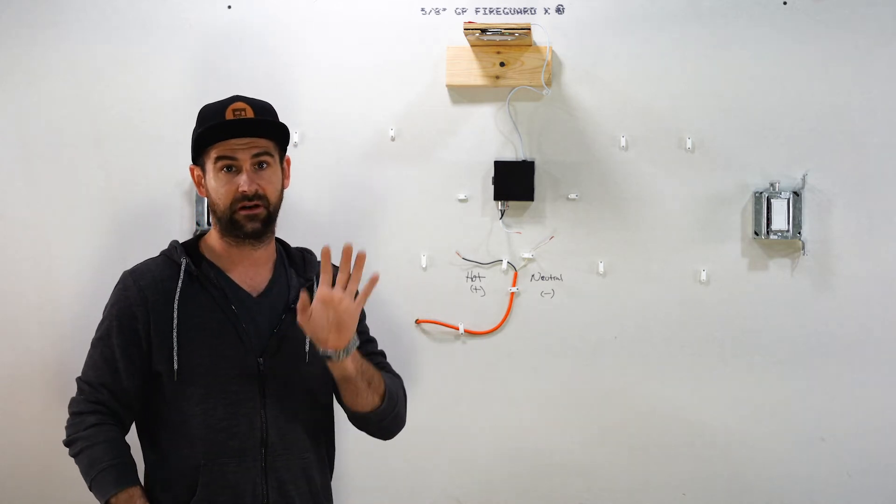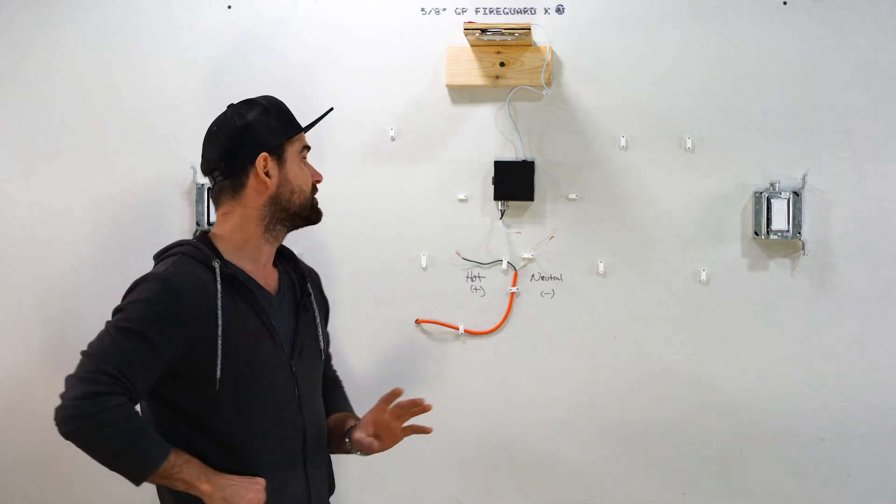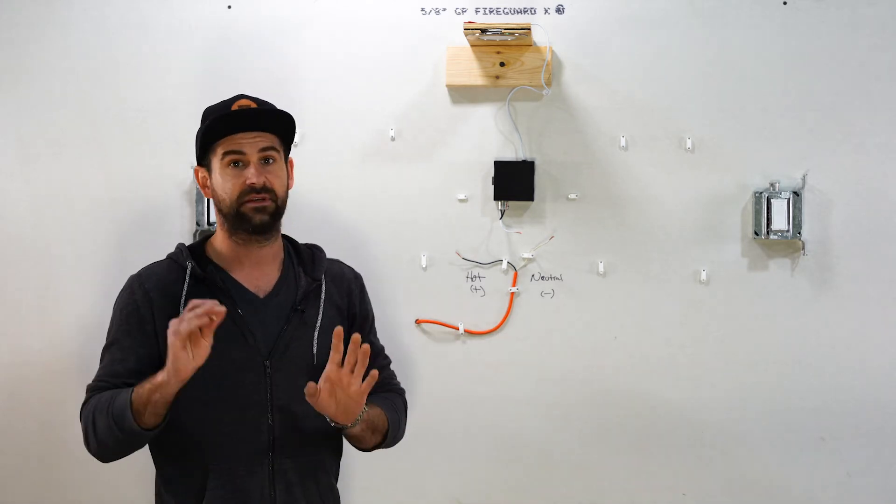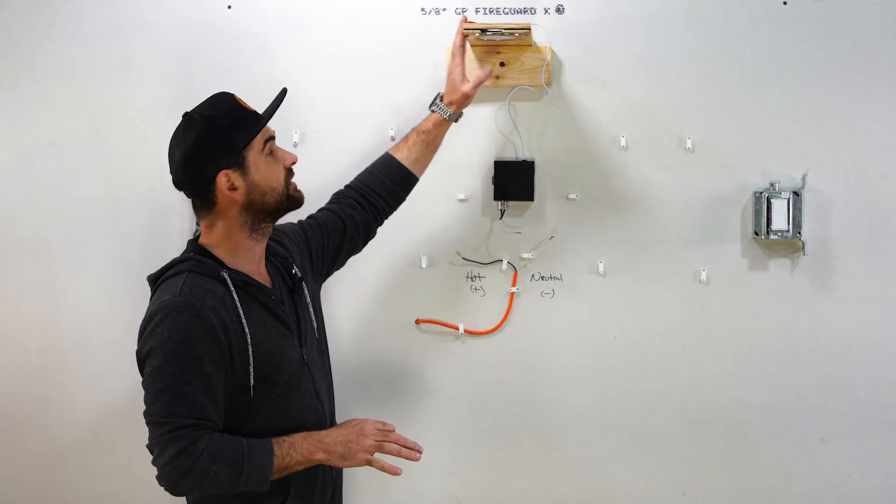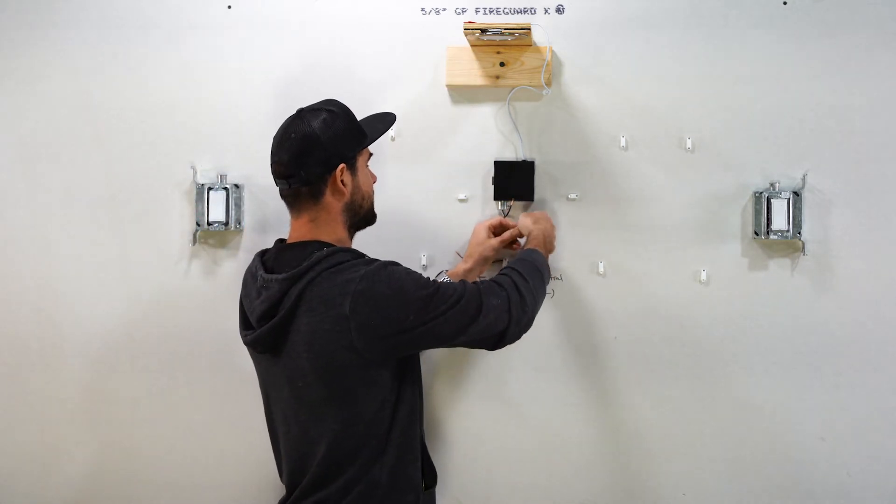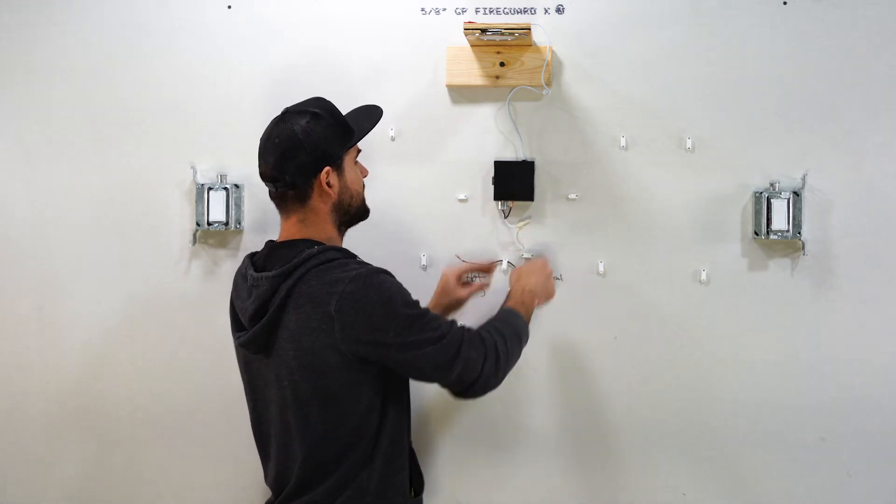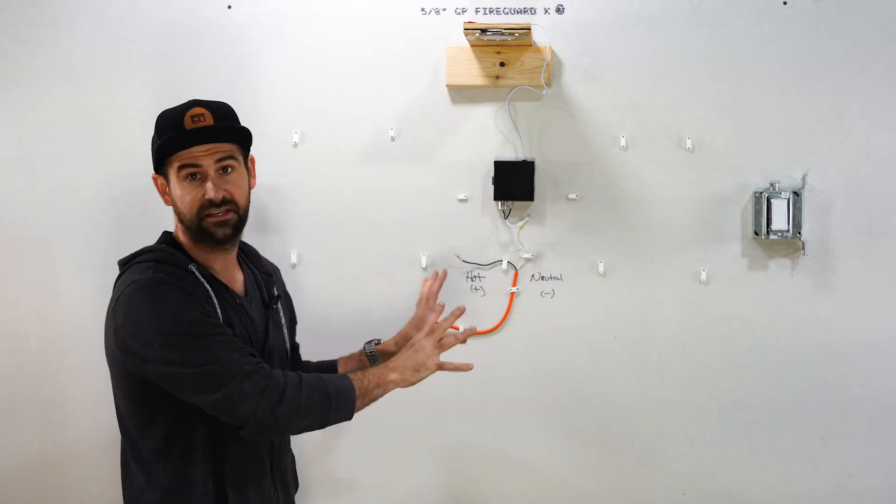So the first step that I always try to get out of the way when it comes to switches is we get the neutral out of the equation. So in this case the only thing that needs to be connected to a neutral is going to be the light fixture. So we're going to take the white from the light fixture and that's going to get connected to the neutral. See the easiest way to do this is start to eliminate what you already have existing right here.